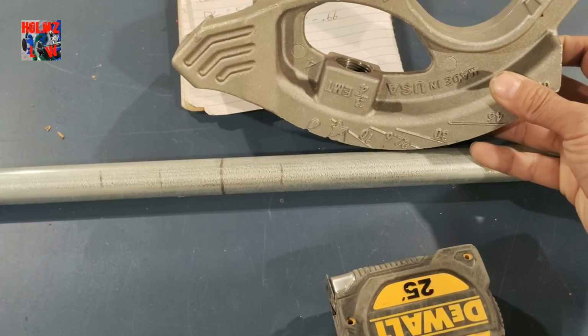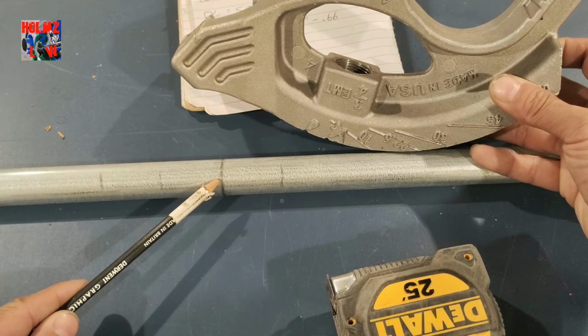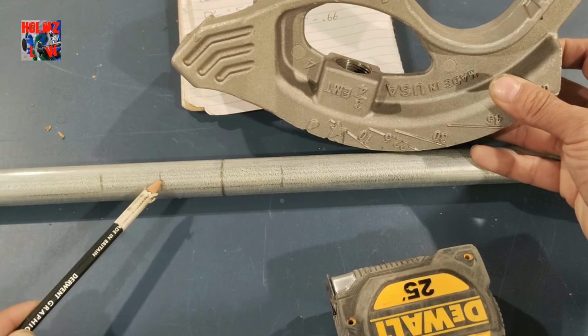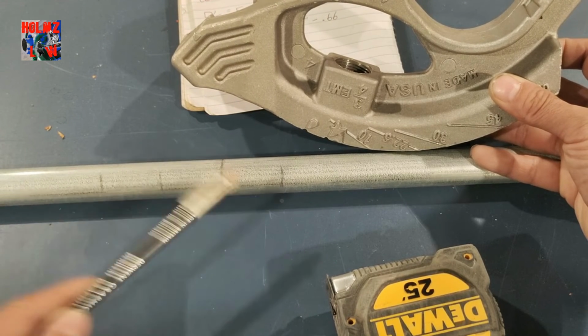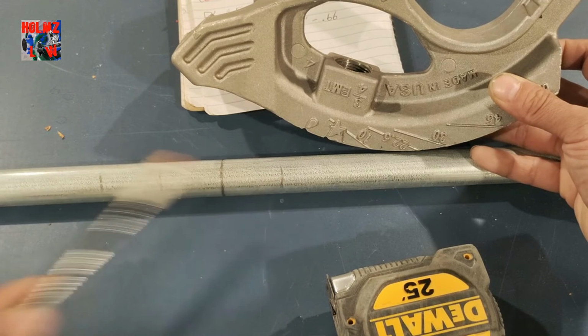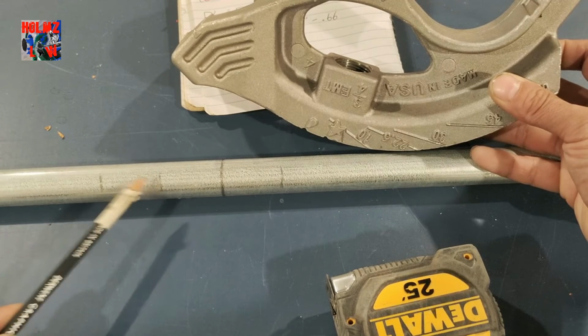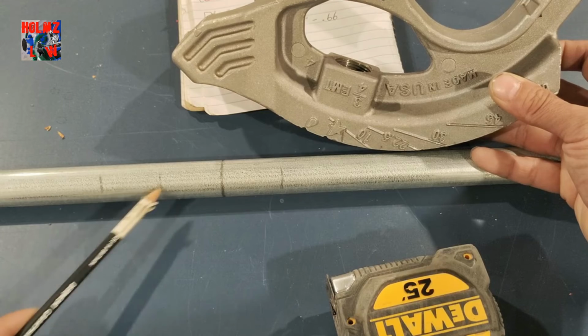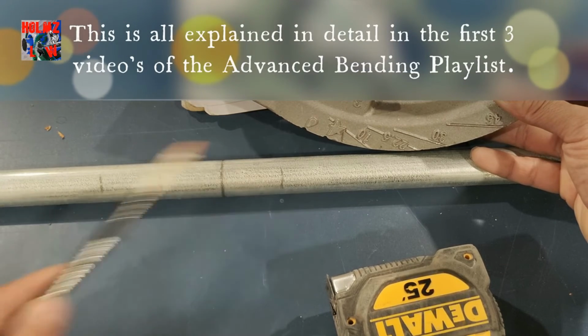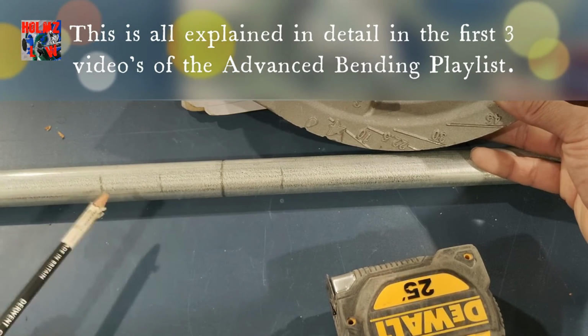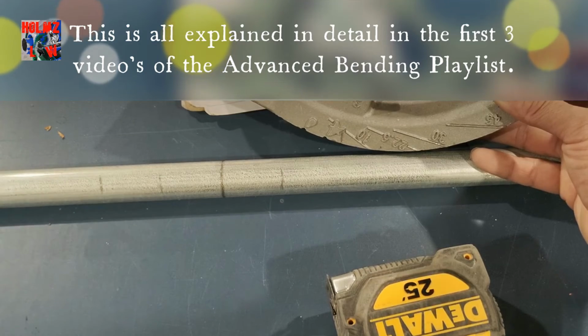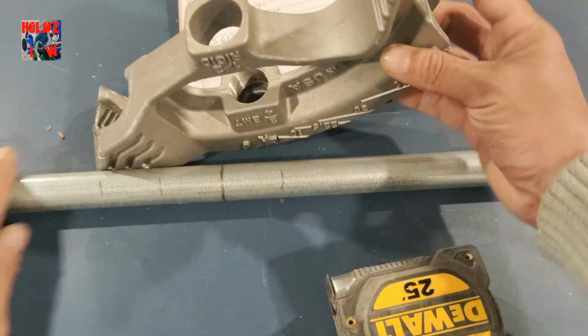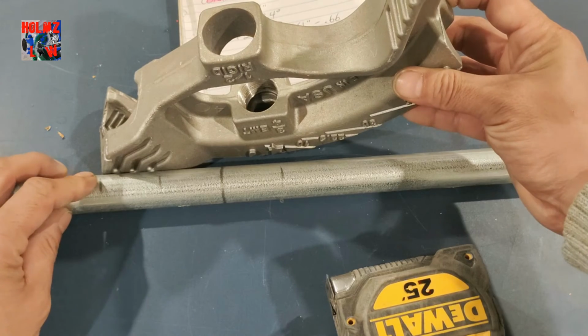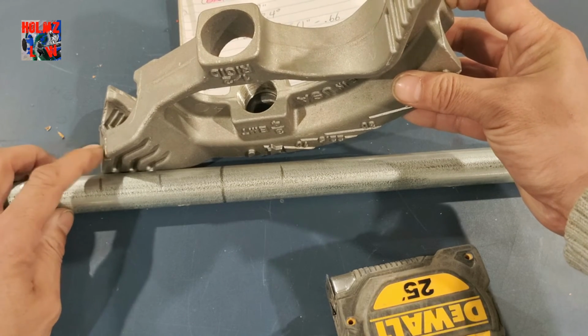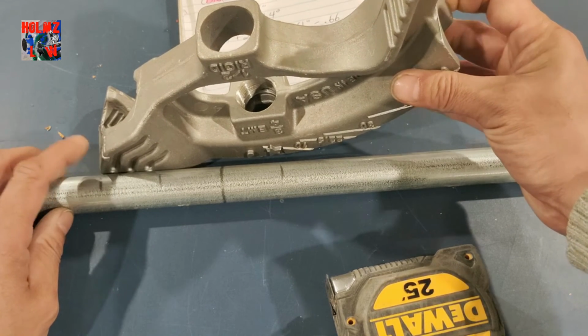All right, you have these 2 marks here. You have your center of the bend, and then we just did the developed length, which this is the start of the bend, and this is the end of the bend. And we just added 1.5 inches, which is our front of hook measurement, to the start of the bend. Depending on which way you want to bend it, you add that front of hook measurement. What that's going to do is let us line up that front of hook measurement with the front of the hook of the bender, or whatever bender you're using.